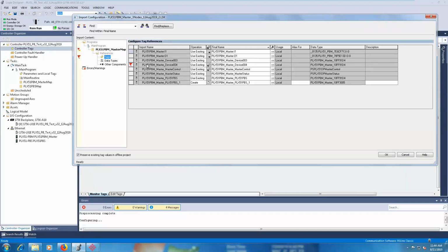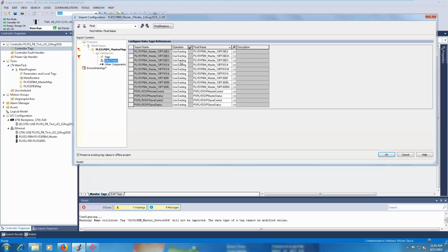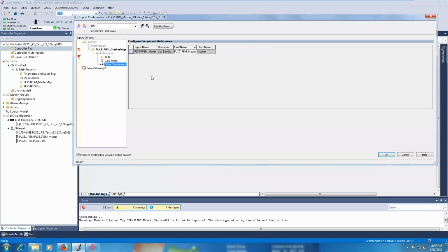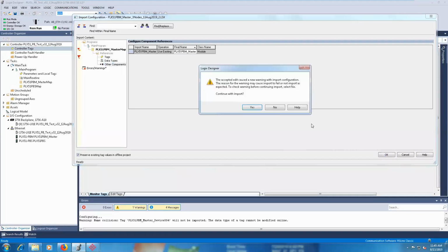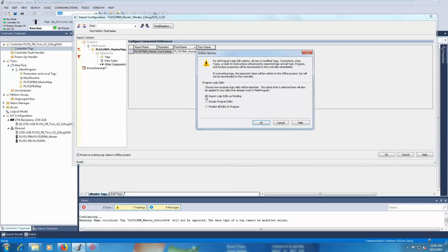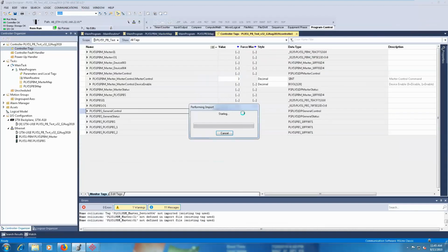Within the environment, it tells me what changed right here. I've got a red flag right here, so I would want to make sure that I overwrite that. And then as far as all of my data types and my other components, those are all good. I can go ahead and tell it yes. And I can import my logic edits as pending. I can accept them, or in this case, I'll just finalize them and import the routine right there. And so this will import my custom configuration file. And it takes just a second to implement this.